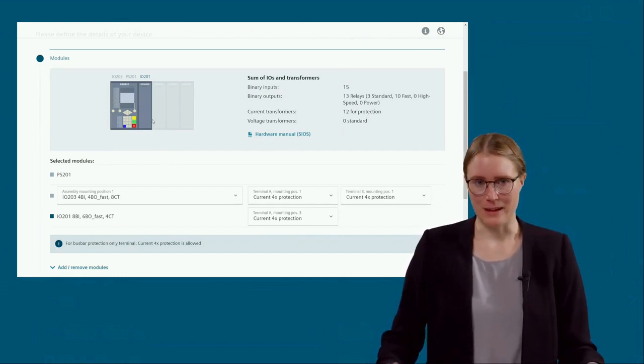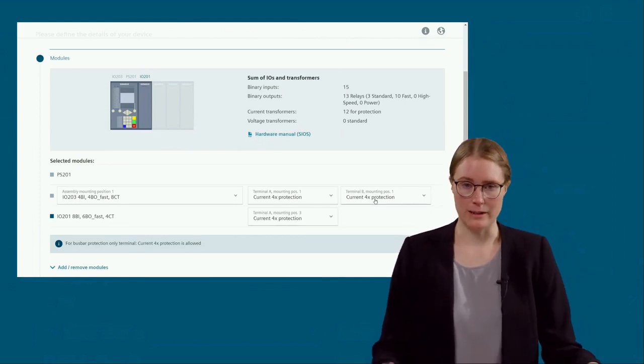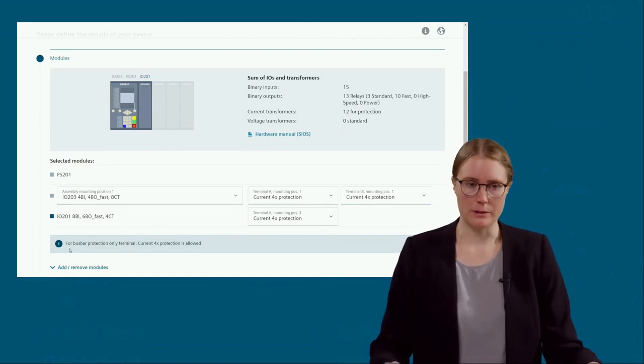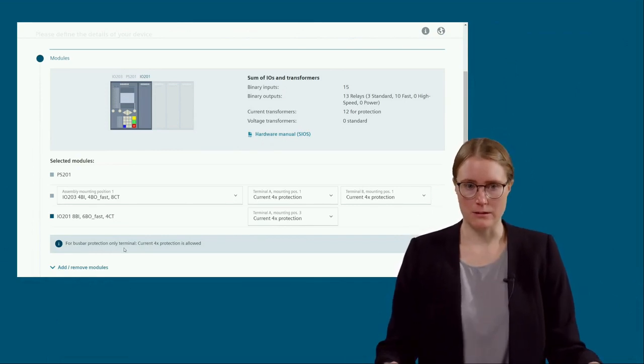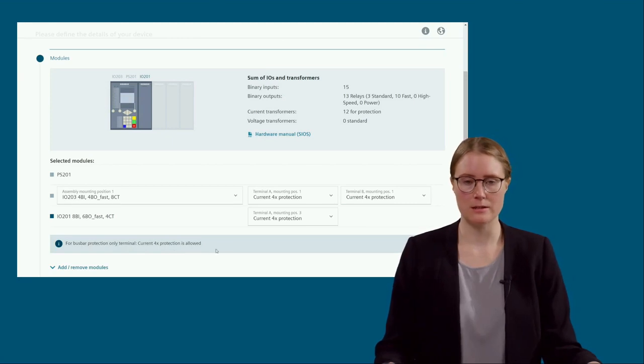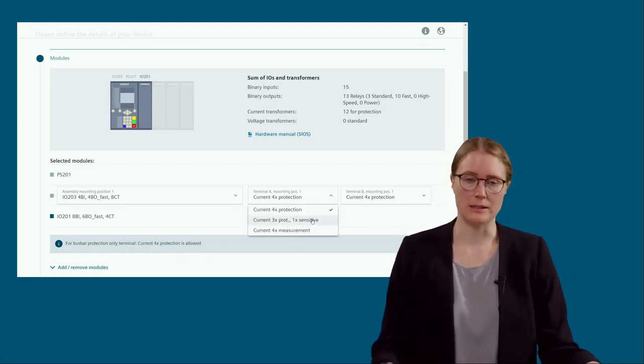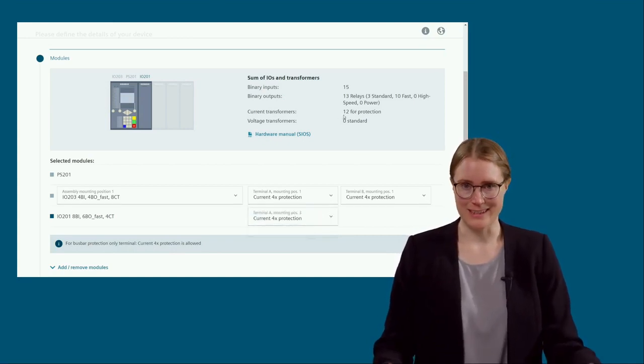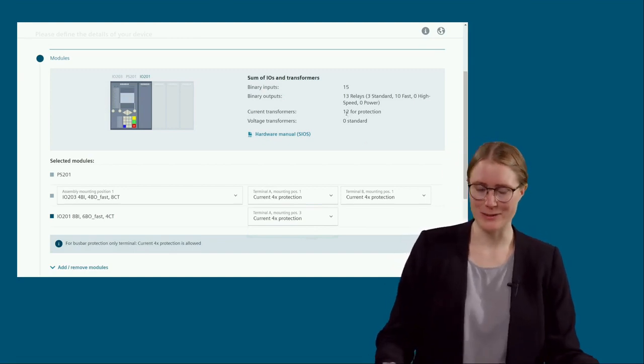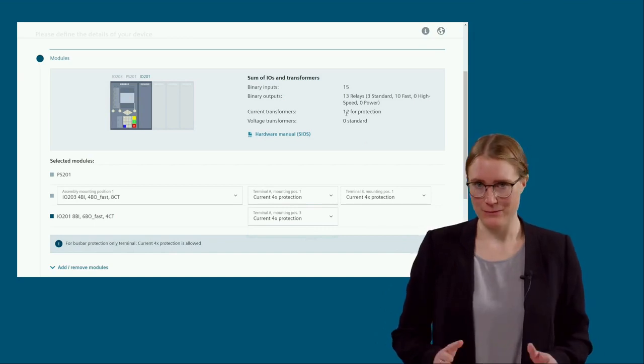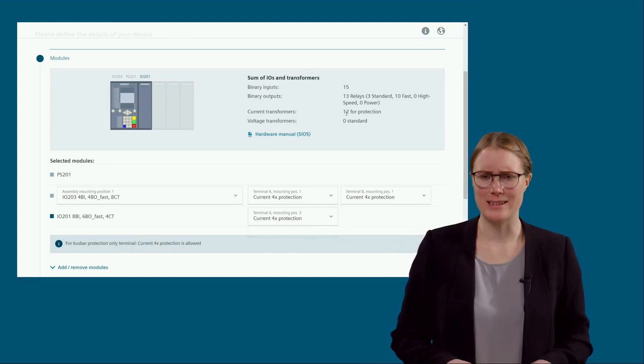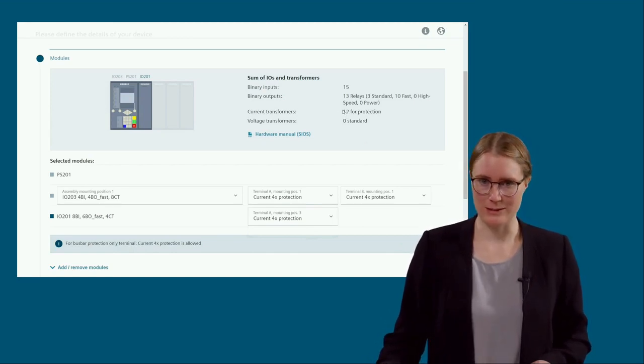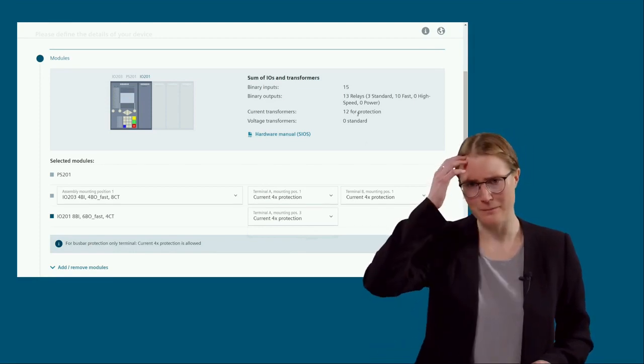Here you can see our device already has 1 base module and 1 additional extension module, IO201. So with this standard variant 1, there are already 3 current input terminals available. And here is also a very important hint on the slide that for busbar protection, only terminals with current 4x protections are allowed. So please make sure that you select the right option here. Okay, but in this case, we have 12 current inputs. This is not sufficient for our example. As we said, we had 5 current measuring points, 5 bays in this case. So this means we need up to 20 current inputs, 5 times 4 in this case.